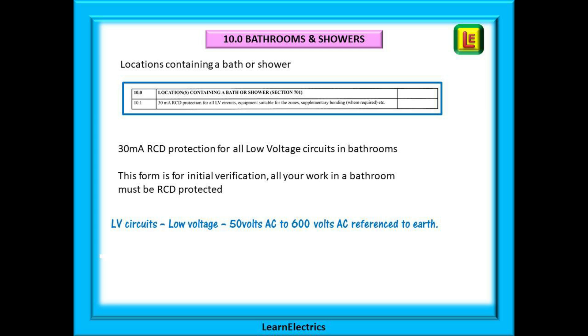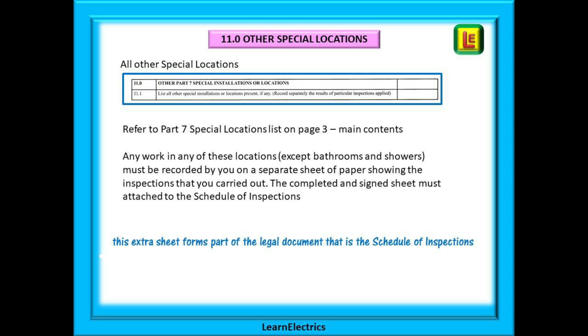Section 10 covers rooms with a bath or shower. The form is for new work — initial verification — and all work in a bathroom must be 30 milliamp RCD protected, as RCD protection is now required for all low voltage circuits in bathrooms or showers that are new or that you have worked on. Section 11 covers all other special locations except bathrooms and showers.